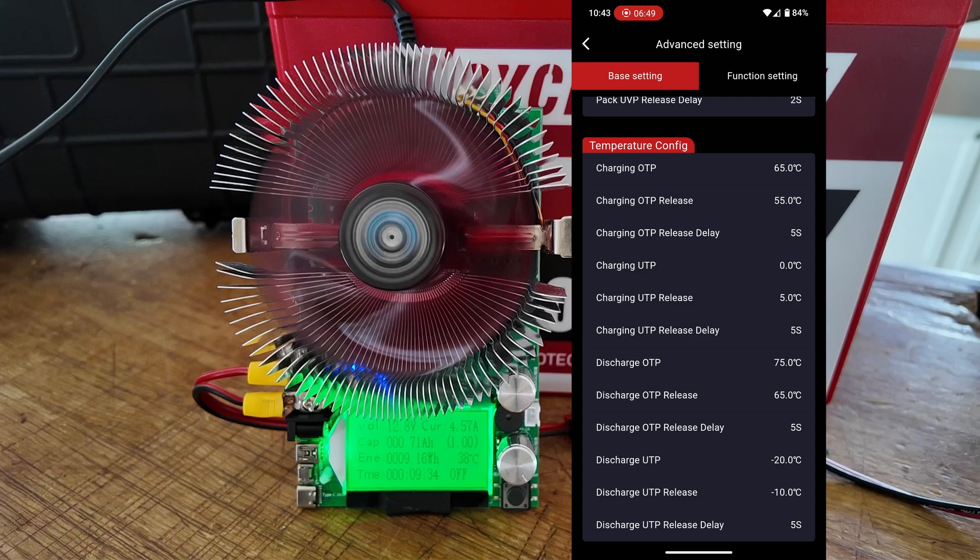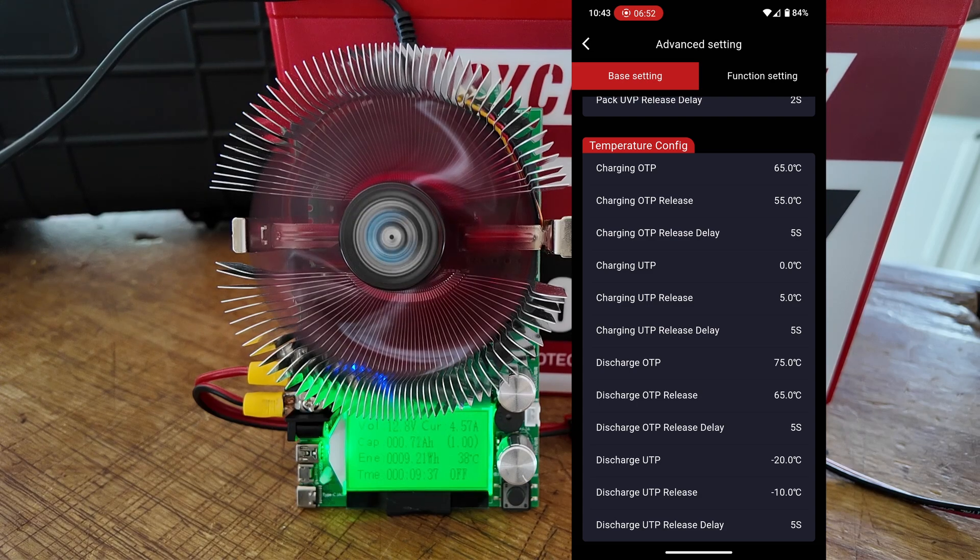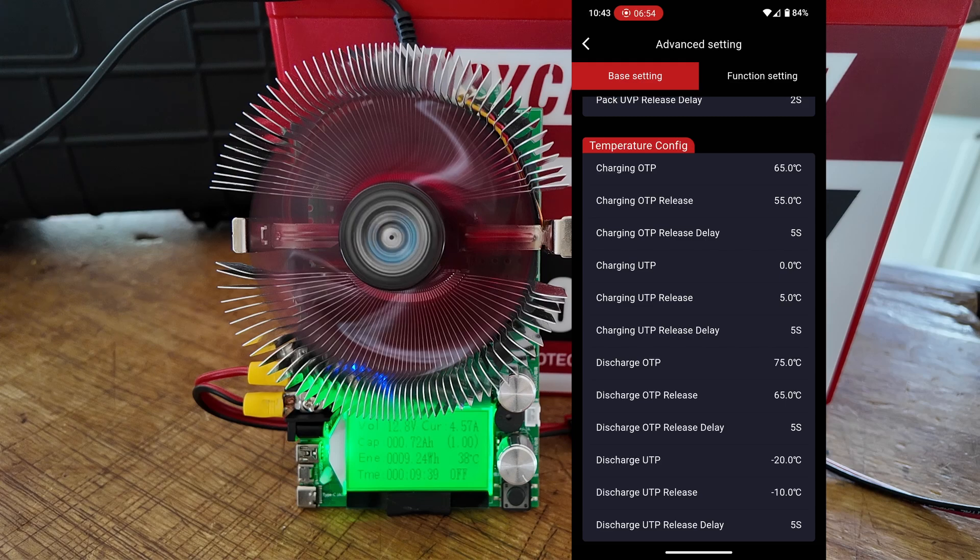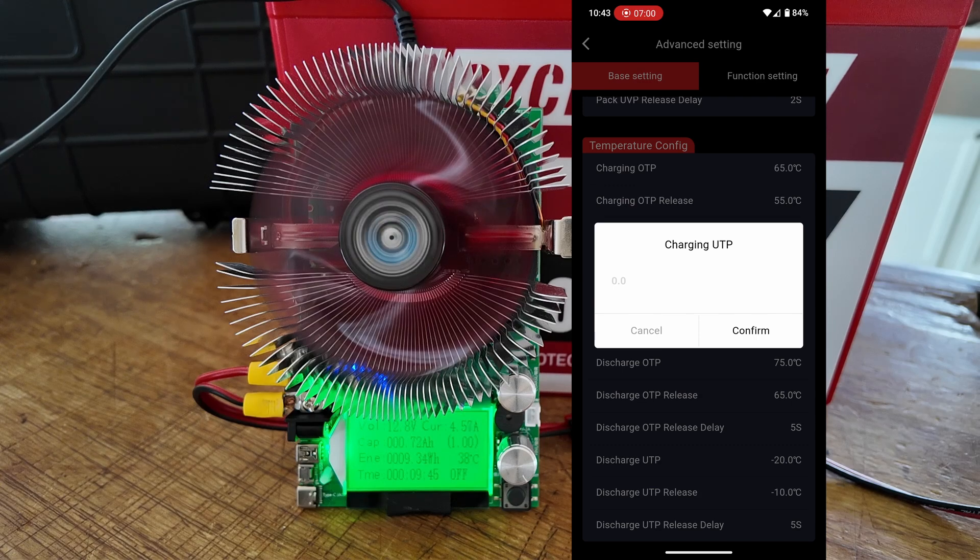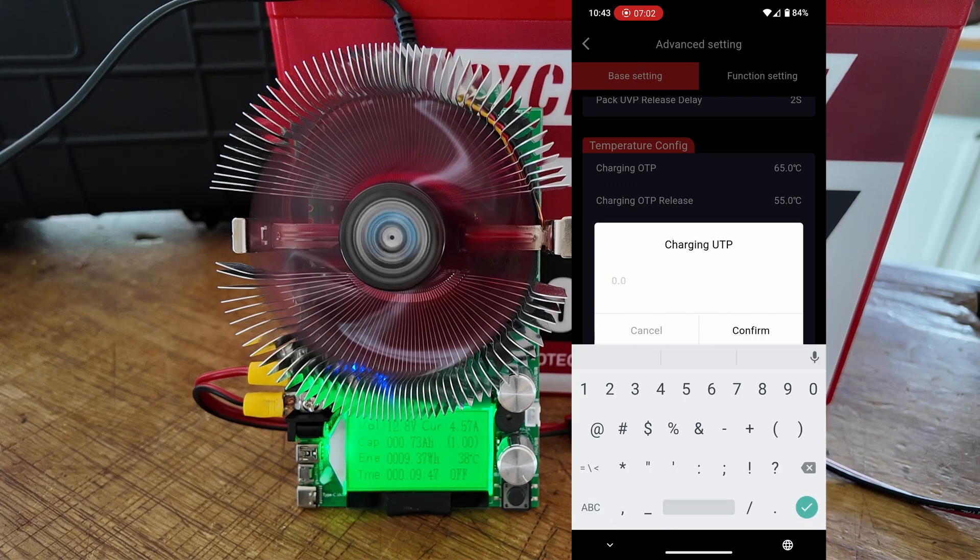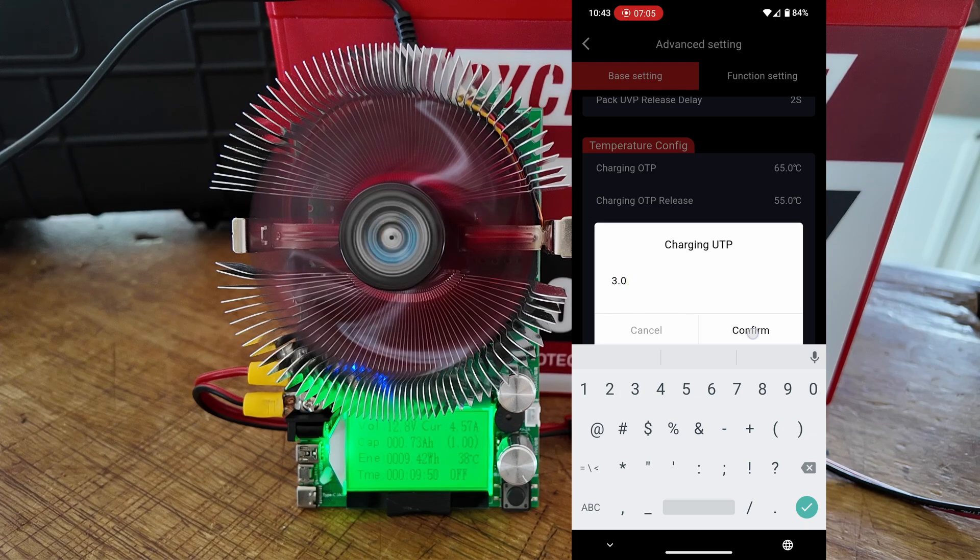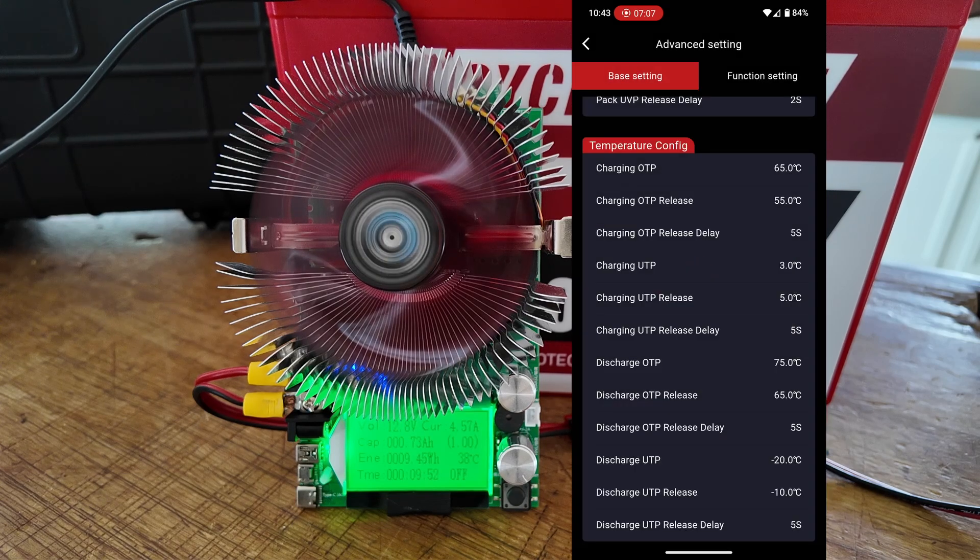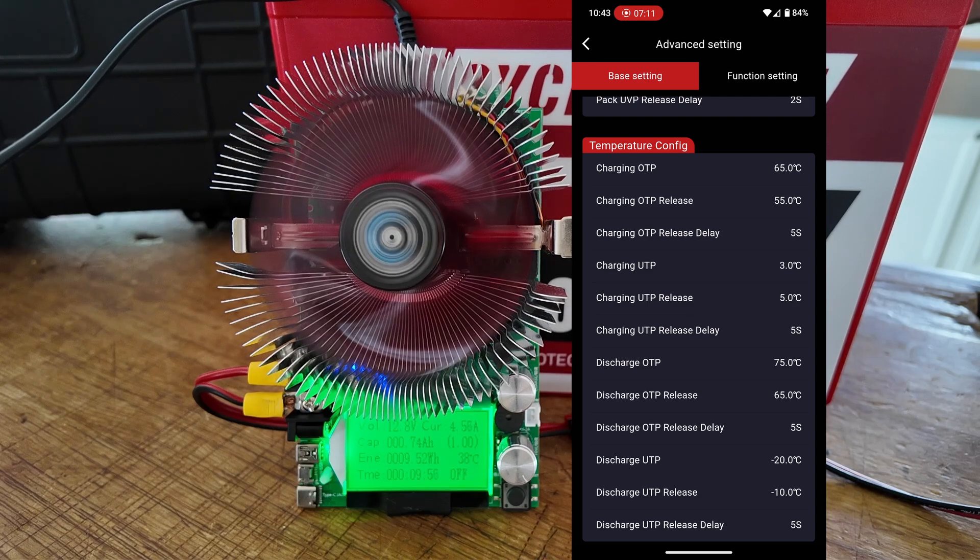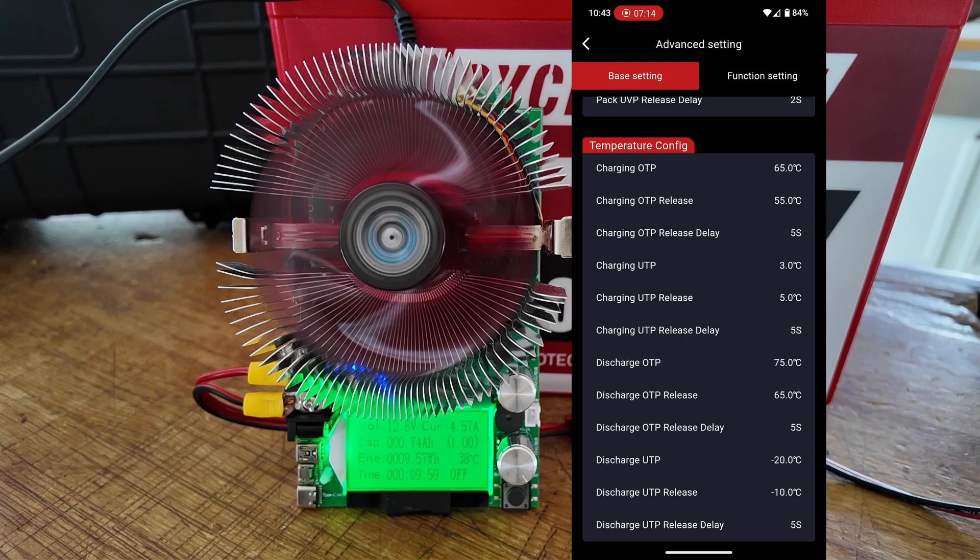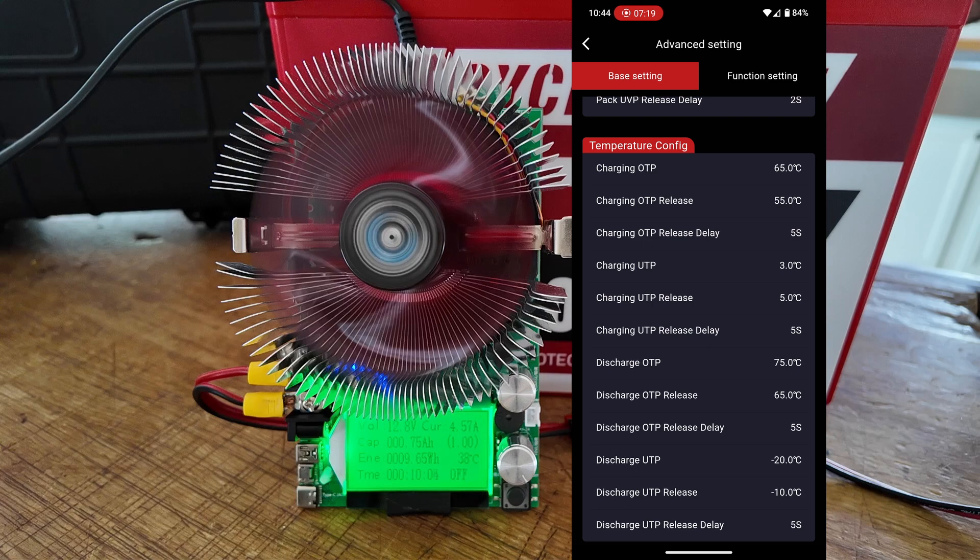Now, for a little bit of extra safety in there, I might bump that up, the under-temp charge protection, to let's say 3 degrees Celsius. If we want to do that, you just simply highlight that and you put in your new value. We'll give it 3.0 and click Confirm. Now it's going to update, and you'll see that if it gets below 3 degrees Celsius now, it's not going to allow me to charge it, and it won't take a charge until it gets back up above 5 degrees Celsius.